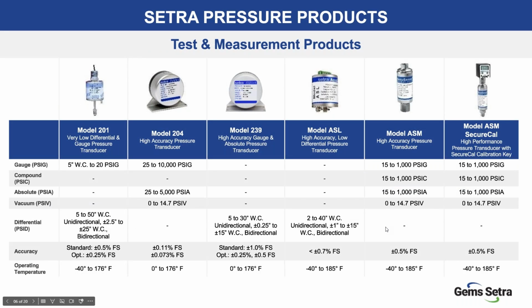With this, we've developed a suite of products, 6 different variations, starting with model 201, able to measure gauge and differential pressure across a broad range while maintaining accuracies of 0.25%, followed by model 204, which spans the broader pressure range up to 10,000 PSI. That provides a single pressure output with higher accuracies of as low as 0.073% full scale.